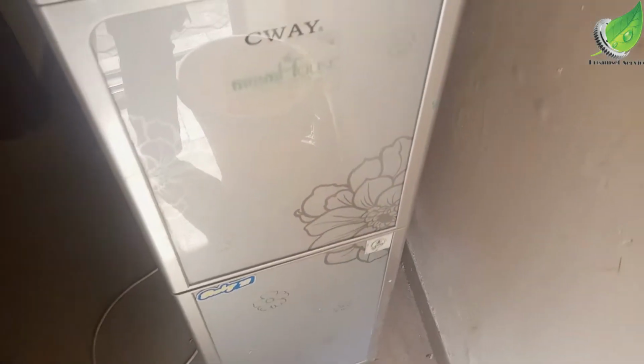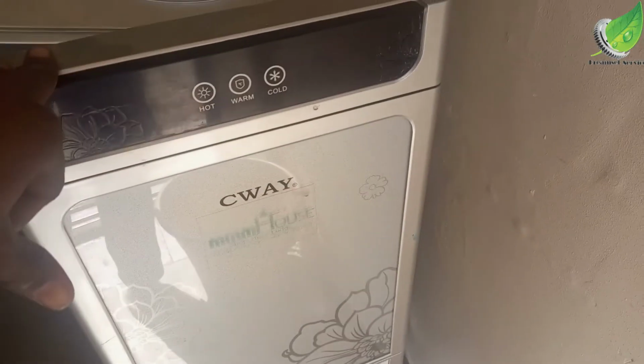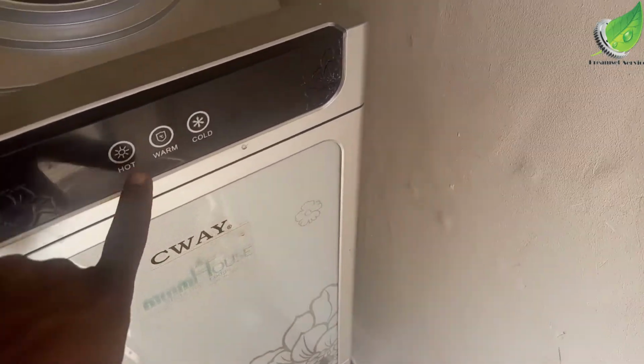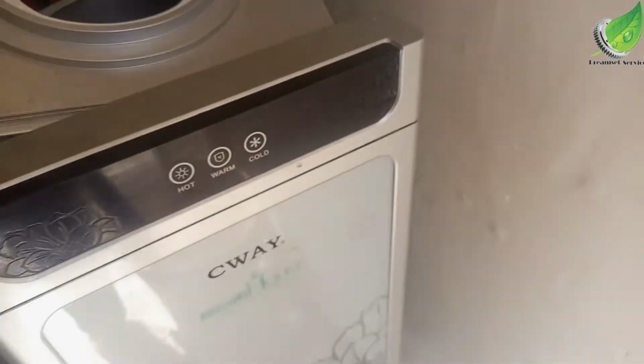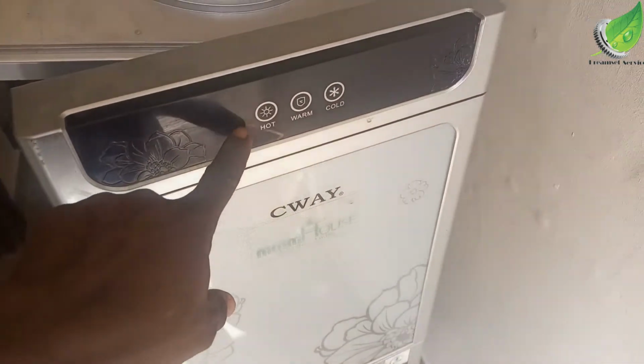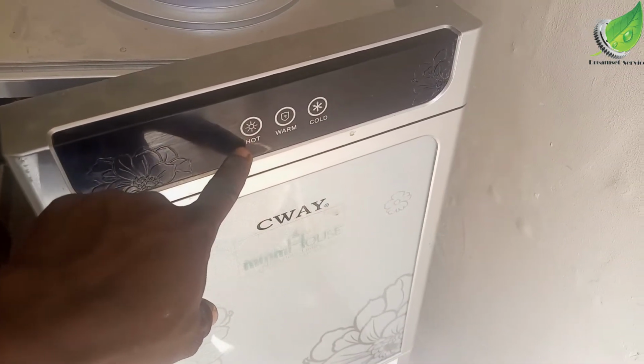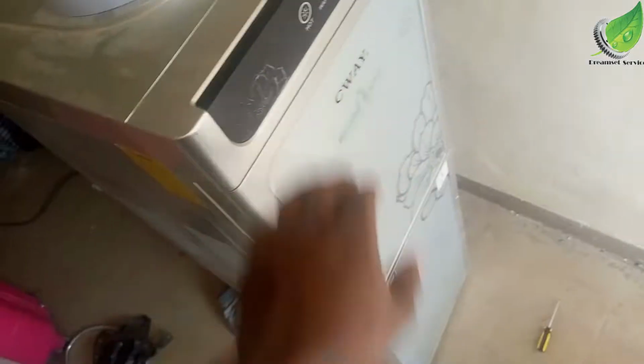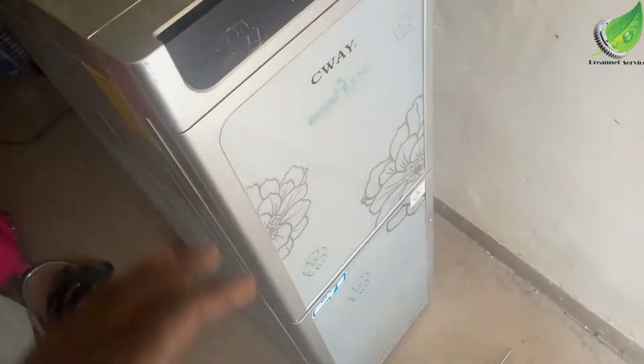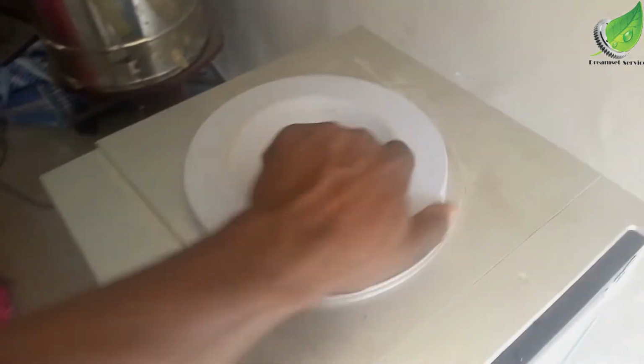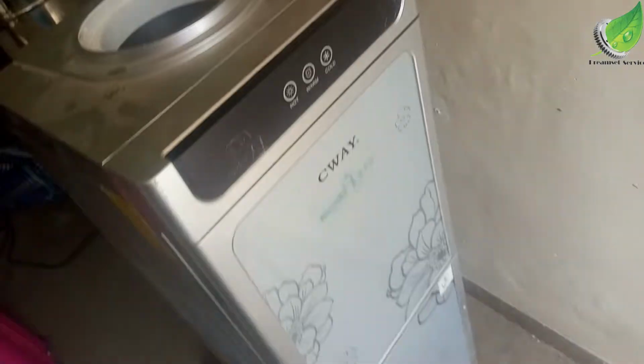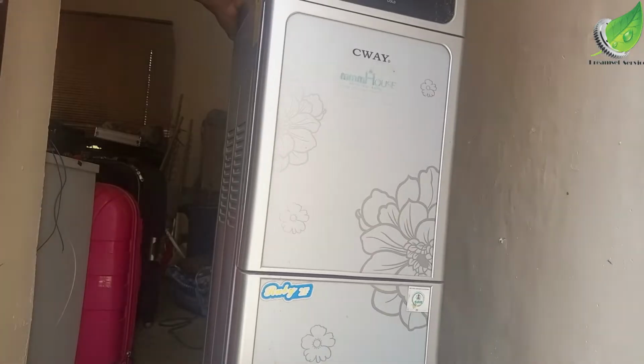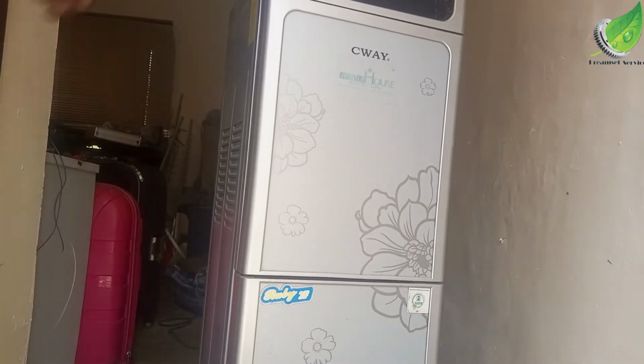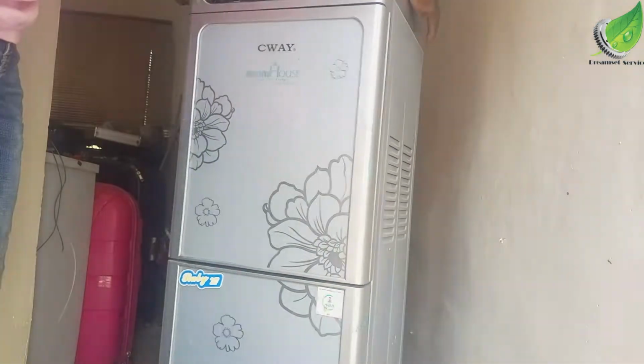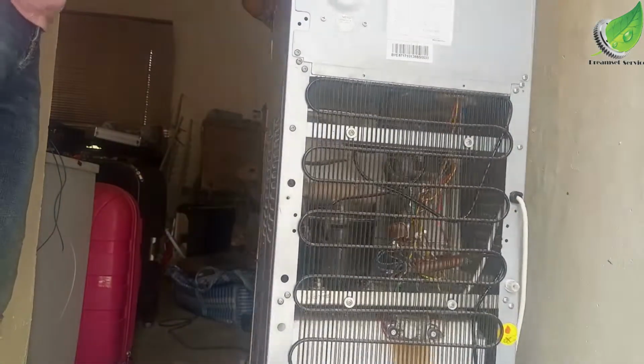So this is a water dispenser and the hot water area is not working, only the cold is working for now. From this water dispenser we have cold, warm, and hot, but the hot area is not working at all. So what I'm going to do is show you what the problem is and how to correct it. Most of the time it just has to do with the thermal sensor that controls when the dispenser switches off the hot water area and switches it on again.